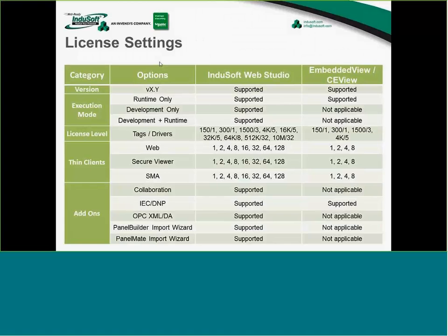We have different names for these products, but regardless of the names, the limitations are pretty much what you can see here. So it's defined by the number of tags and then the number of drivers that you can run simultaneously. So, for instance, if you buy the basic license, that would be 150 tags, one driver running. Now, the important thing is it can be any of the drivers, right? So as long as you only have one running, you are good with that.